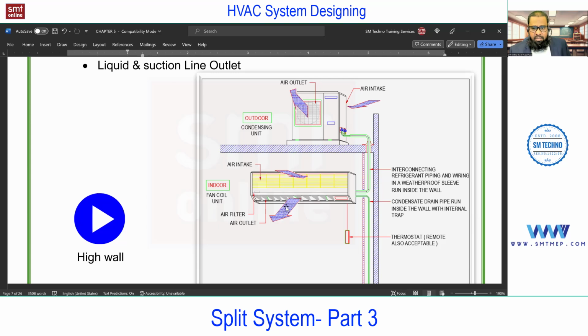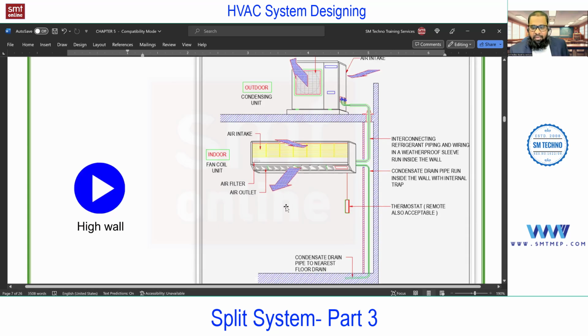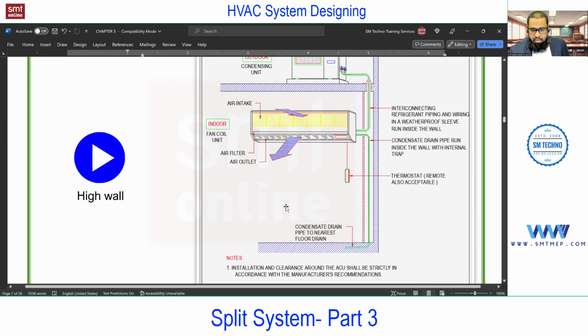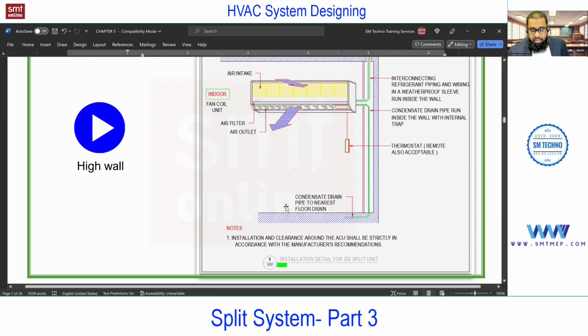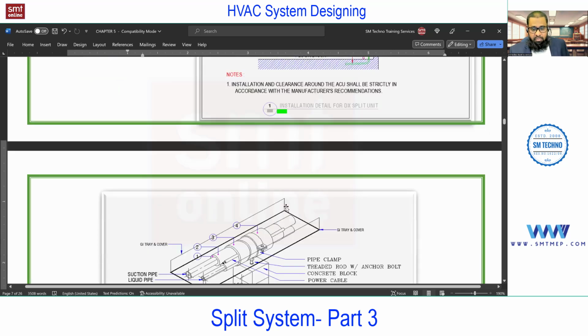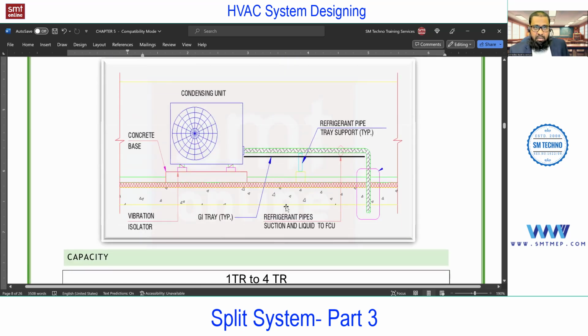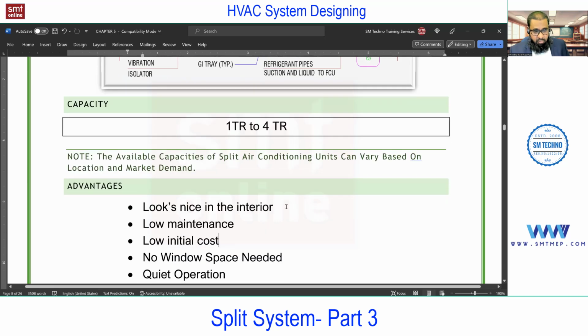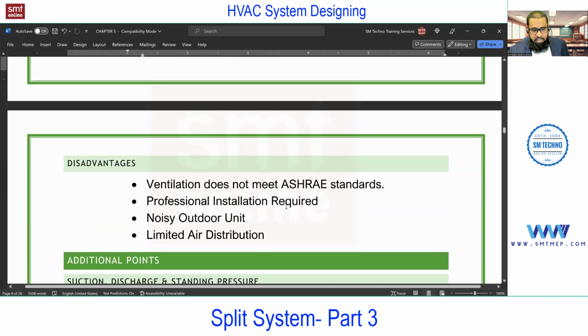But to overcome this, one can open the window partially. We can open the window so that fresh air will be introduced, because this is for small rooms, no? And generally for small rooms, you'll find windows which will open to the outside. For large space areas with multiple spaces without windows, if you use this, that will definitely affect health, because you know the importance of ventilation, which we already discussed at the starting session, maintaining the oxygen level. So the major disadvantage in the window or in split is that ventilation is not as per standard.